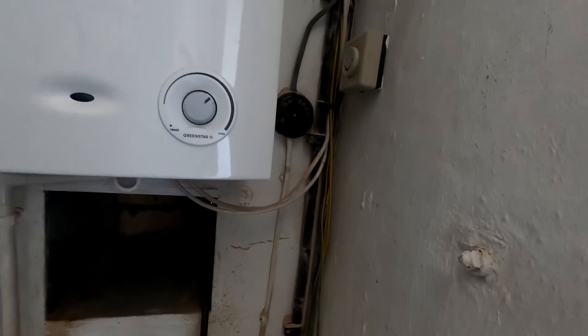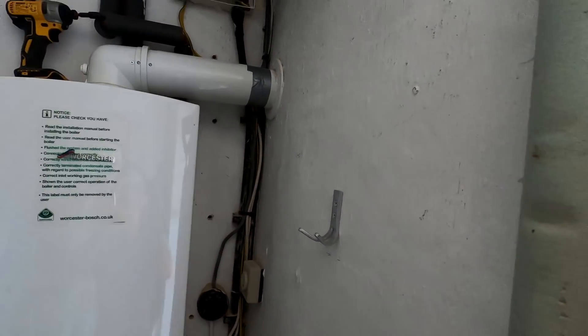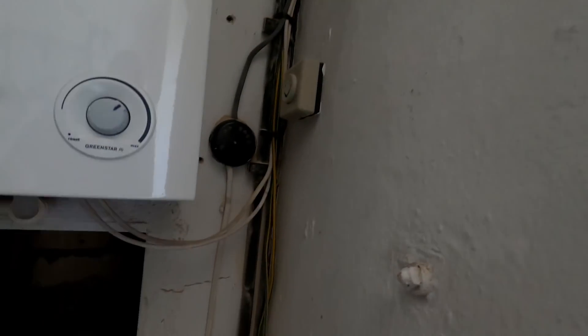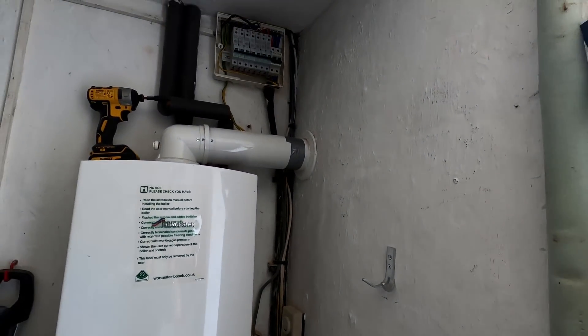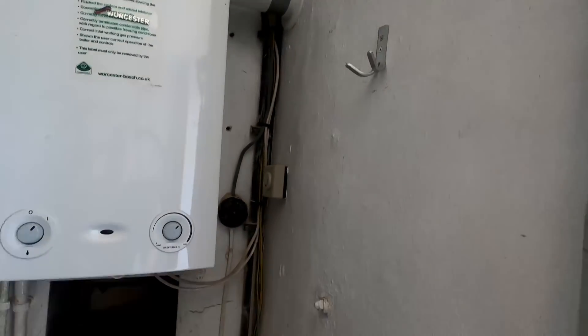Where the cables were damaged, we've been able to pull enough slack from the boiler because they had a massive drop-off loop. We pulled it back through and just Wago'd it with a junction box in the ceiling, so that's done thankfully.